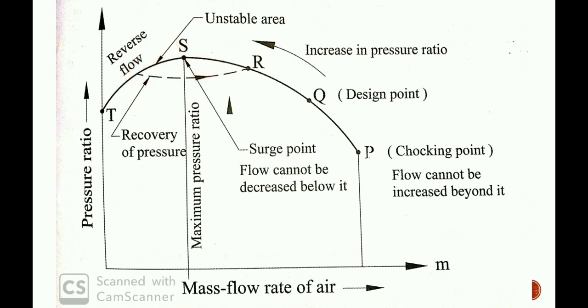The physical damage from surging is due to high impact loads and high frequency of vibration. When there is pressure oscillation and reverse flow, it causes essential effects to the compressor: pressure shock and tripping of the compressor, resulting in mechanical damage — damaged blades and casing.